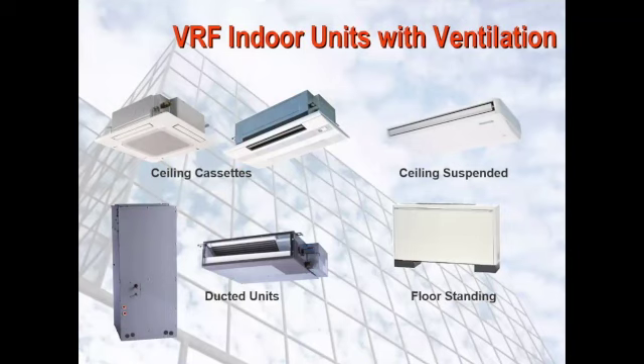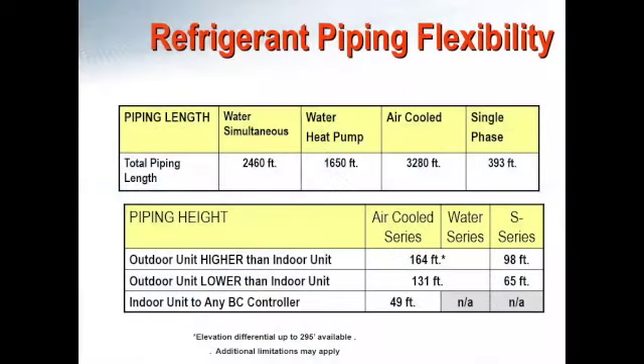With the new Local Law 97 kind of codes, the group of codes that's been passed into New York City law recently, there's also a new economizer code, which is going to require a lot of VRF units, or really a lot of indoor units, to accept ventilation. So these are all of the units that most typical manufacturers can provide that are going to be able to accept ventilation. Really, the only units that are not capable of accepting ventilation are going to be the standard wall-mounted unit and the similar unit that is going to have a really good air throw.